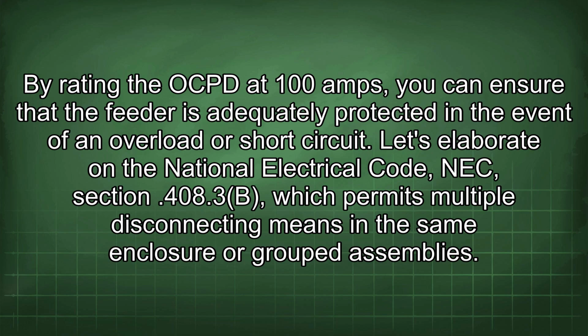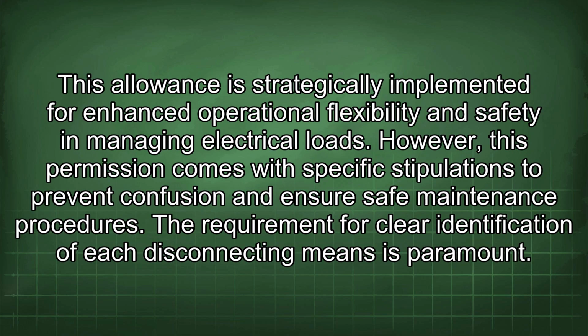Let's elaborate on the National Electrical Code, NEC, section 408.3b, which permits multiple disconnecting means in the same enclosure or grouped assemblies. This allowance is strategically implemented for enhanced operational flexibility and safety in managing electrical loads. However, this permission comes with specific stipulations to prevent confusion and ensure safe maintenance procedures. The requirement for clear identification of each disconnecting means is paramount.